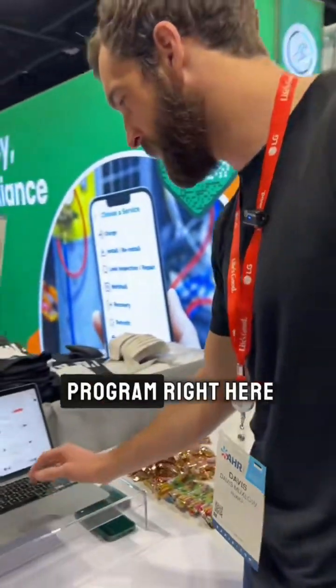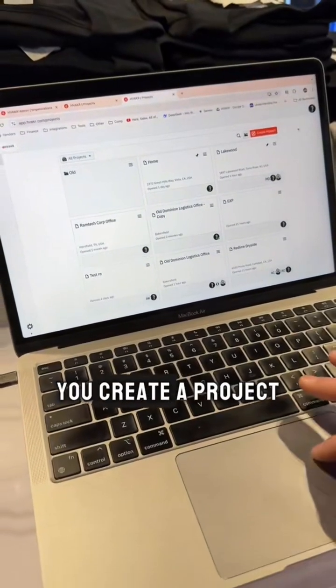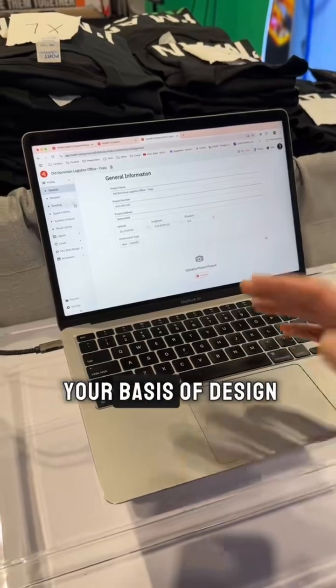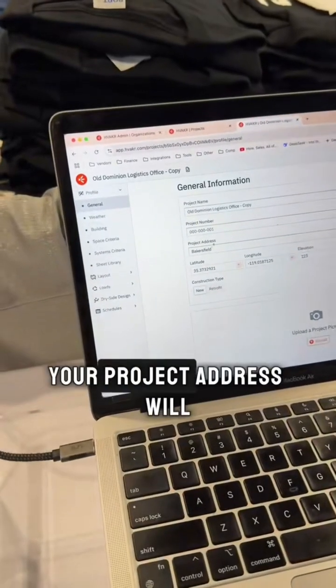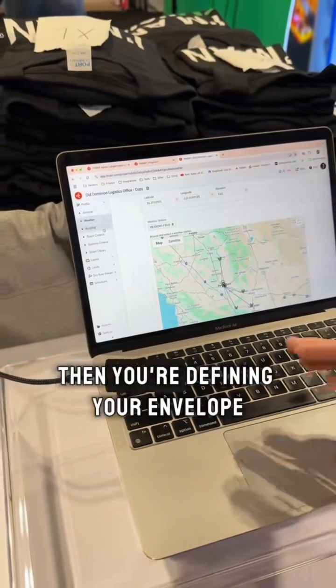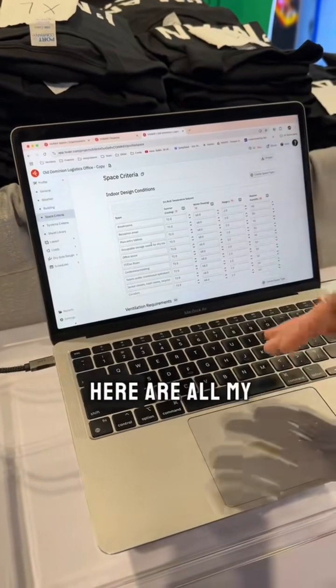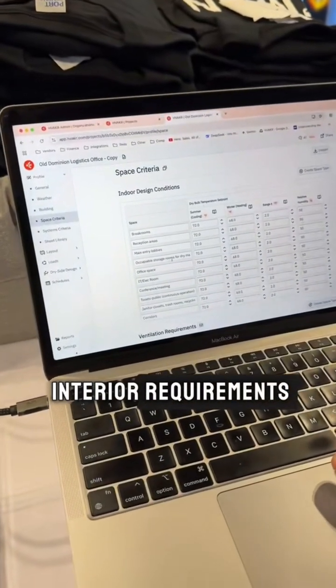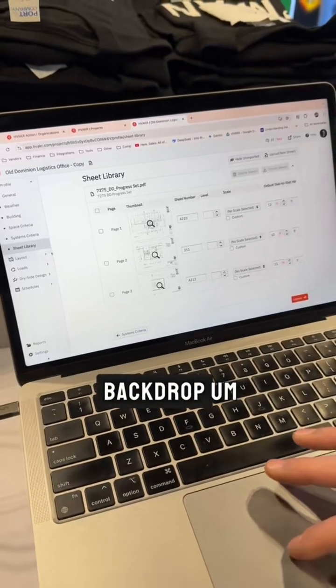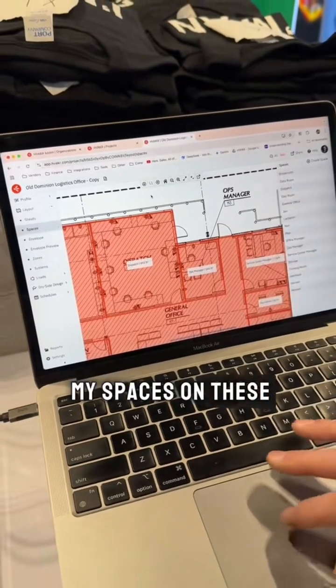So this is the program right here. It's a cloud-based application for doing HVAC design. You create a project — I'll jump into one now. The first few steps, you're setting up your basis of design. Your project address will get you your weather stations and weather data. Then you're defining your envelope: wall types, window types, the space criteria — all your interior requirements. From there, you upload a set of floor plans, which becomes the backdrop for your design, and you take off your spaces on those floor plans.